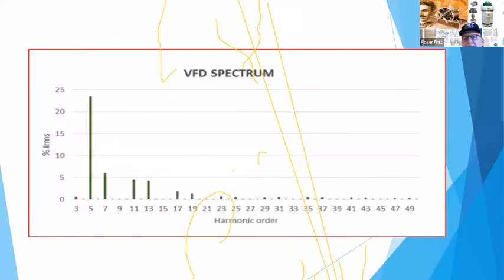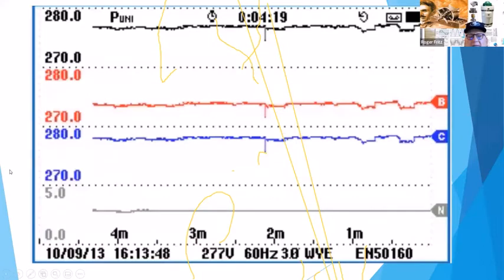So this is a look at those spectrum frequencies that show up, and these are the percentages of the current, the RMS percentage. So if you're drawing 100 amps, you'll have, like here, up at 23 amps of that are fifth harmonic currents, and you don't pick those up on regular meters. And so it's important that you are aware of that. We'll get back to that. That's about looking at a voltage spectrum.